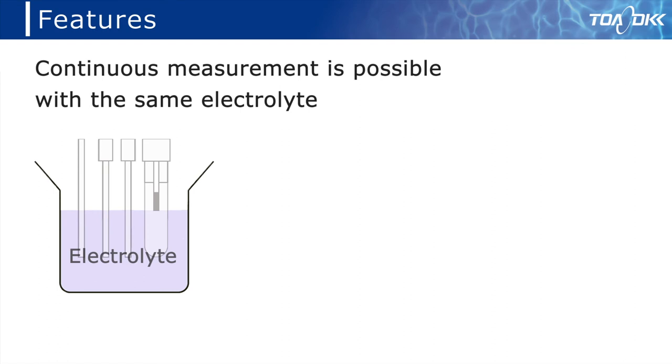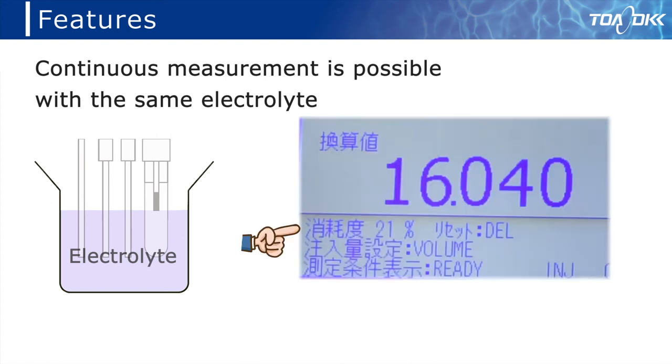You can make continuous measurements with the same electrolyte, but the electrolyte will gradually wear out. The degree of consumption of the electrolyte is displayed on the screen, so you can know the guideline for replacement time and ensure stable measurement.